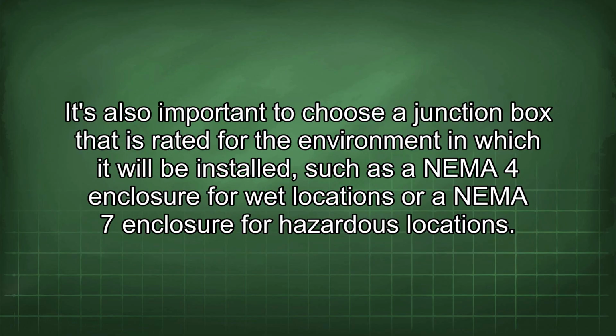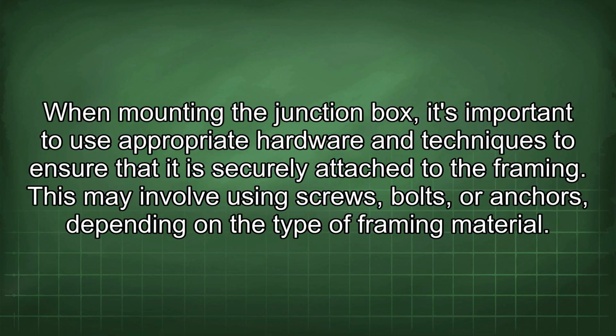It's also important to choose a junction box that is rated for the environment in which it will be installed, such as a NEMA 4 enclosure for wet locations or a NEMA 7 enclosure for hazardous locations. When mounting the junction box, it's important to use appropriate hardware and techniques to ensure that it is securely attached to the framing. This may involve using screws, bolts, or anchors depending on the type of framing material.